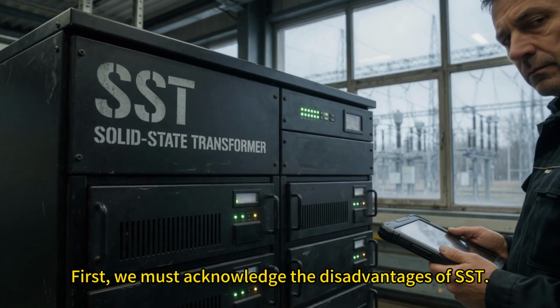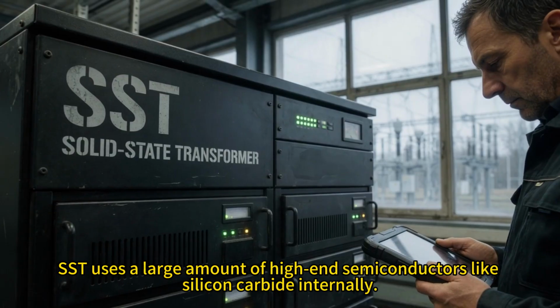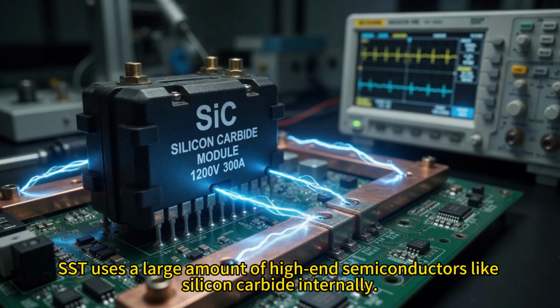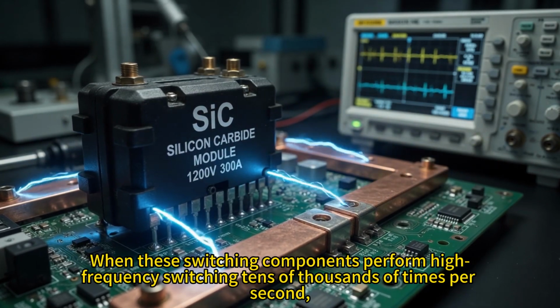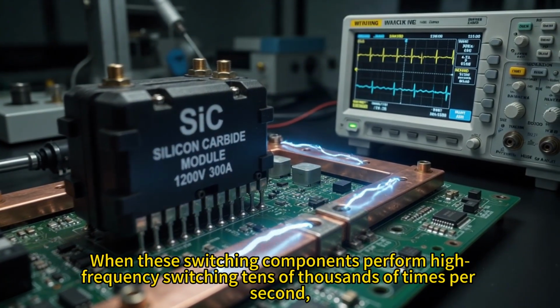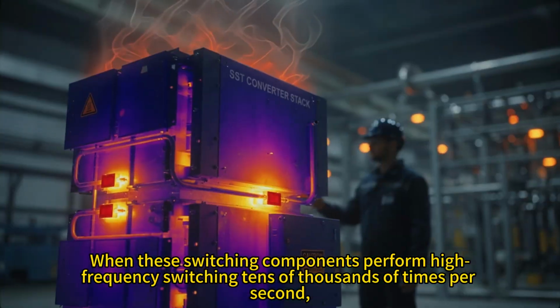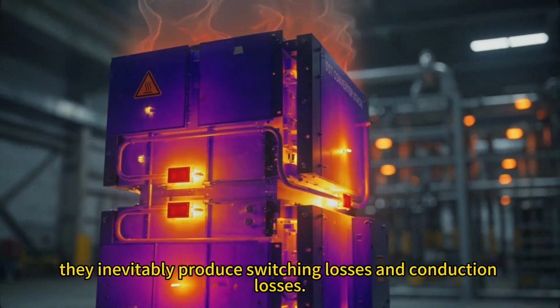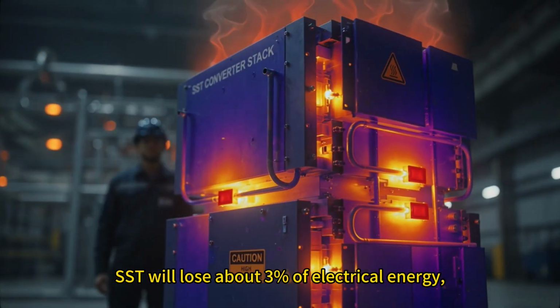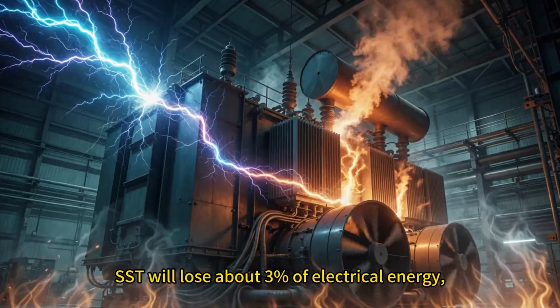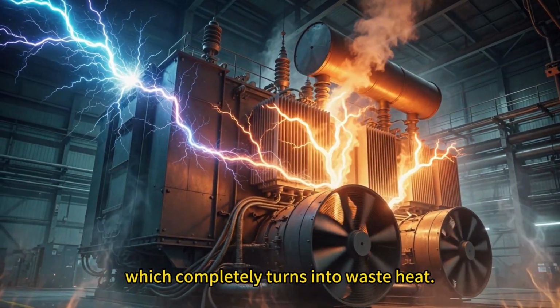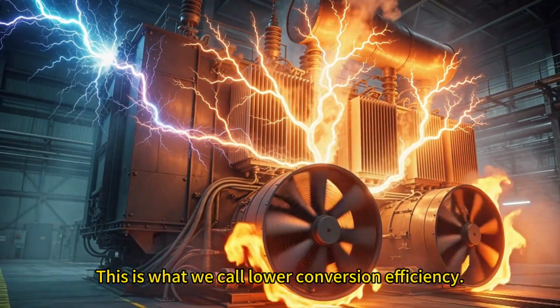First, we must acknowledge the disadvantages of SST. SST uses a large amount of high-end semiconductors like silicon carbide internally. When these switching components perform high-frequency switching tens of thousands of times per second, they inevitably produce switching losses and conduction losses. SST will lose about 3% of electrical energy, which completely turns into waste heat. This is what we call lower conversion efficiency.